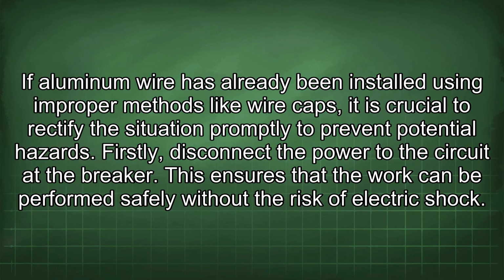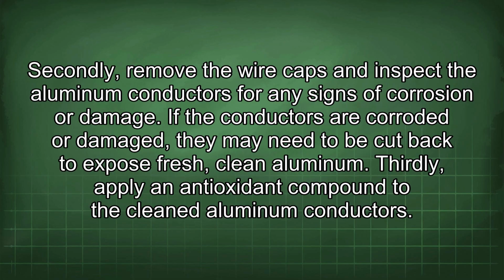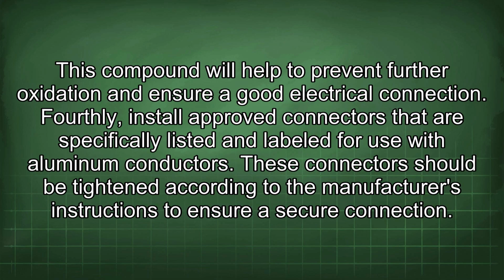Firstly, disconnect the power to the circuit at the breaker. This ensures that the work can be performed safely without the risk of electric shock. Secondly, remove the wire caps and inspect the aluminum conductors for any signs of corrosion or damage. If the conductors are corroded or damaged, they may need to be cut back to expose fresh, clean aluminum. Thirdly, apply an antioxidant compound to the cleaned aluminum conductors. This compound will help to prevent further oxidation and ensure good electrical connection.